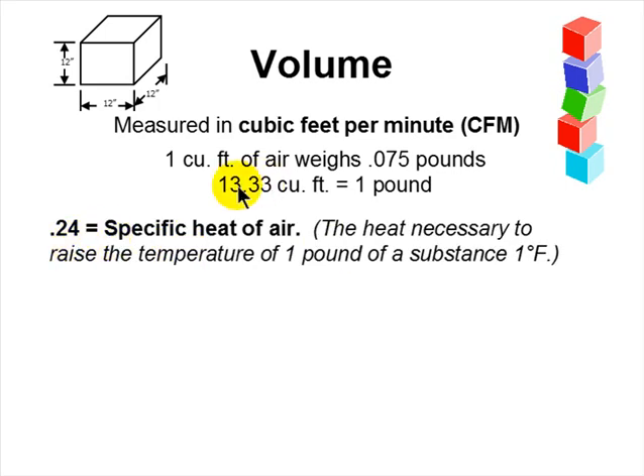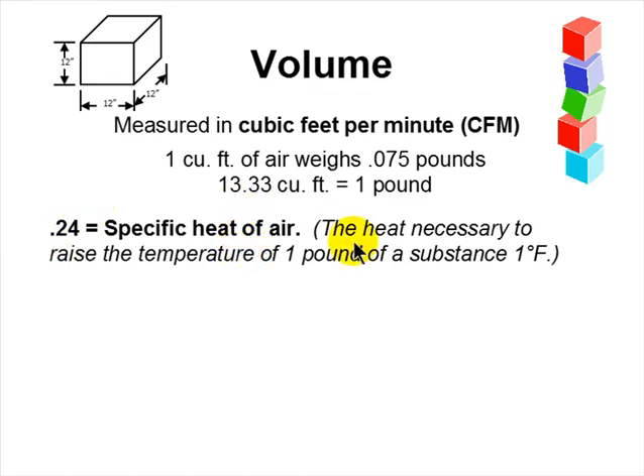Why is a pound of air important? Because we have to deal with the specific heat of this air if we're going to change its temperature. The specific heat of a substance is the heat necessary to raise the temperature of one pound of a substance one degree Fahrenheit. It takes a quarter of a BTU to raise the temperature of air one degree Fahrenheit. The specific heat of water is one — it's the definition of a BTU: the heat necessary to raise one pound of water one degree Fahrenheit at temperatures near freezing at sea level.